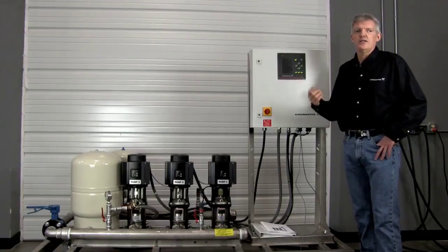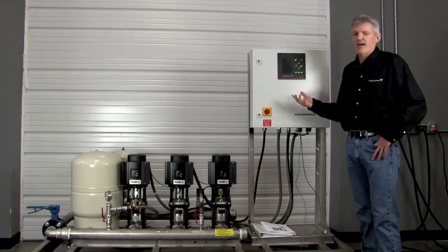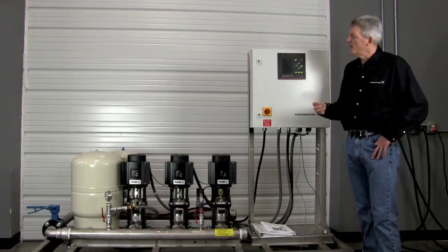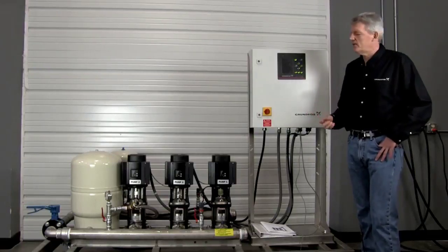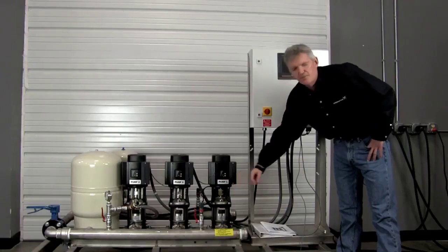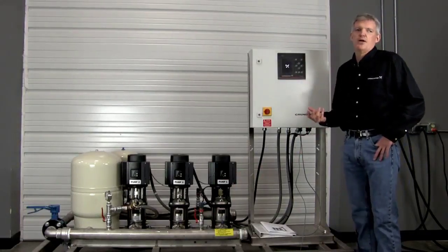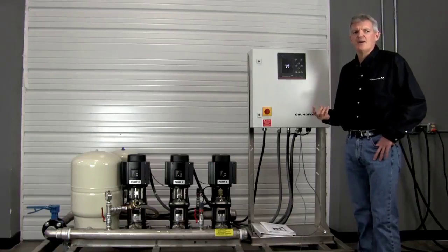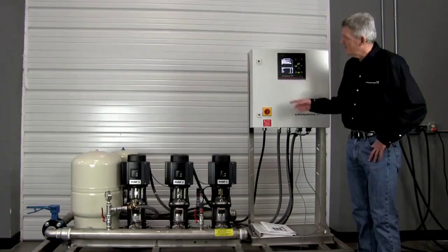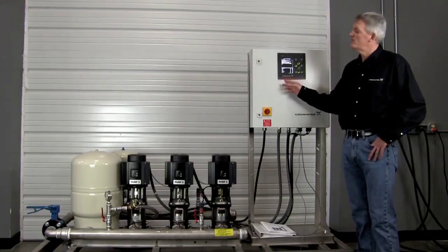The first screen will be the language assignment as part of the wizard. So the wizard has about 26 screens in it, although we can go through that relatively quickly. You notice the pumps will actually come on. You'll see a little light here flashing. That means the pump's in minimum speed. So before the bus grabs control of the pumps, they'll go to minimum speed, which is between 750 and 800 RPMs. And so now we've woken up. Our system is ready to go for Startup Wizard.